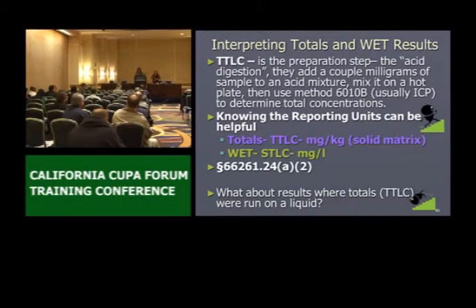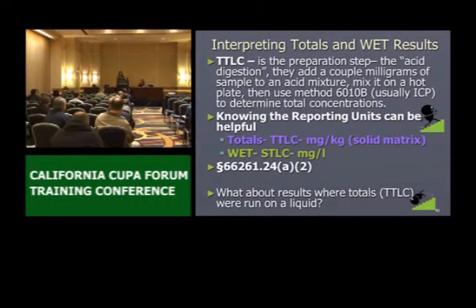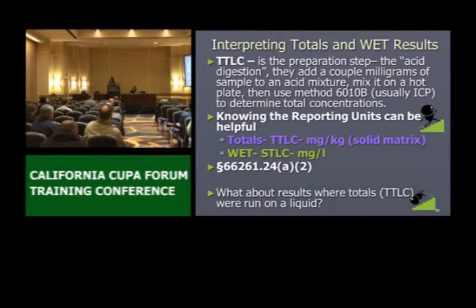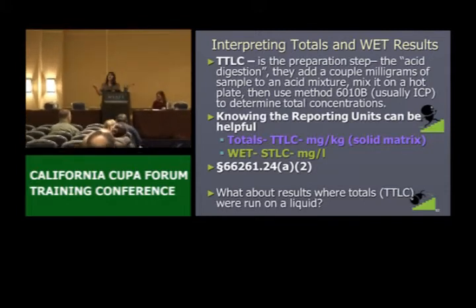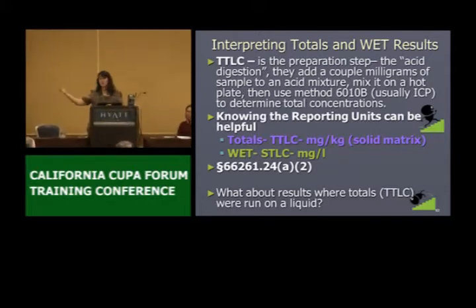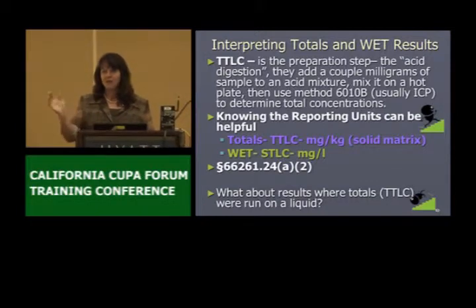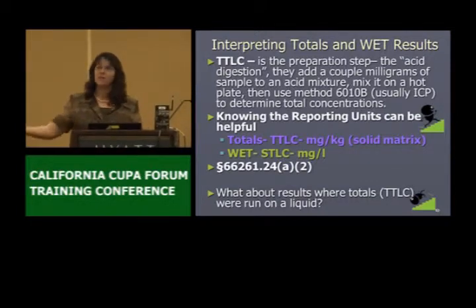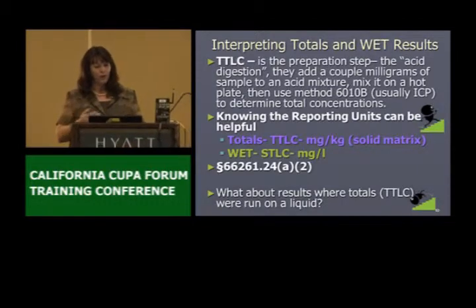Right, so in my example, the facility was this huge facility. For years, since 2000, we've been writing them up for not having PE certifications for their hazardous waste tank system. They had nitric, HF tanks, acid, potassium hydroxide, and all this waste containing metals in the trenches of their facility. They had a big sump containing hazardous waste with heavy metals and corrosives.